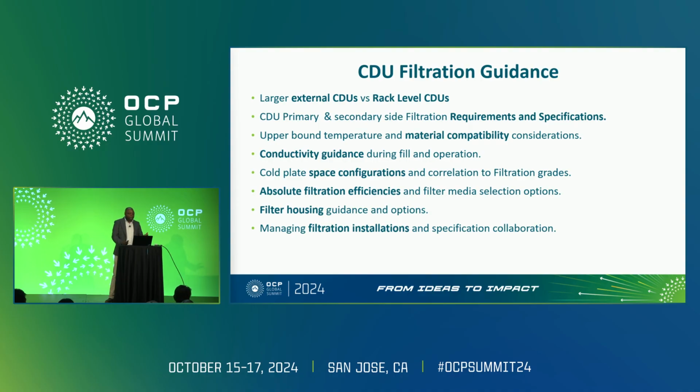The most common filter material that you see out there is polypropylene. But be aware that polypropylene as a material does tend to start to buckle when you approach 65 degrees. So you need then a filter that has a more sturdy core. Typically what filter vendors would recommend would be a glass core to make the filter more integral.